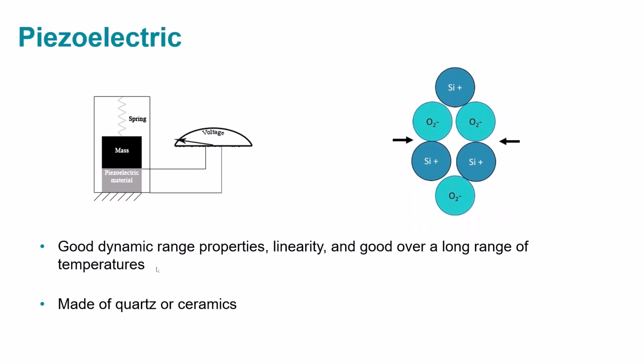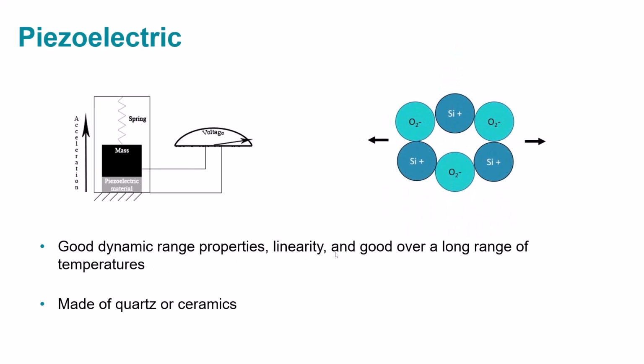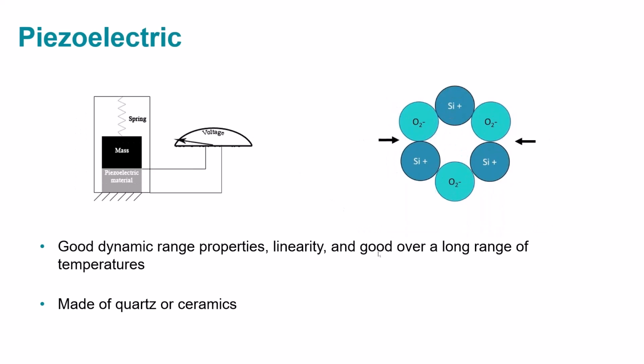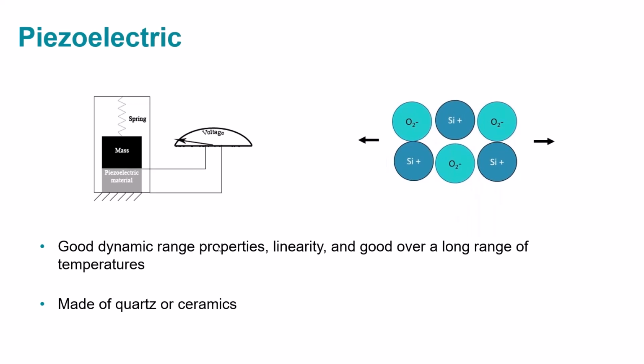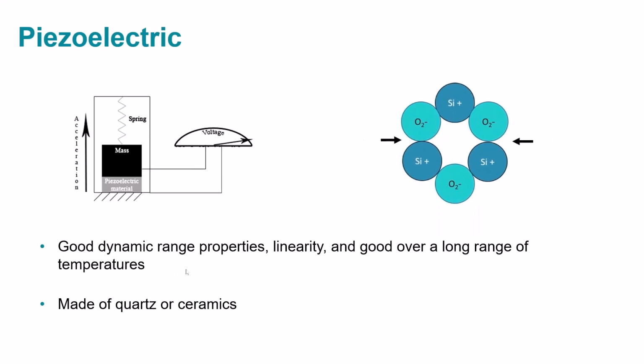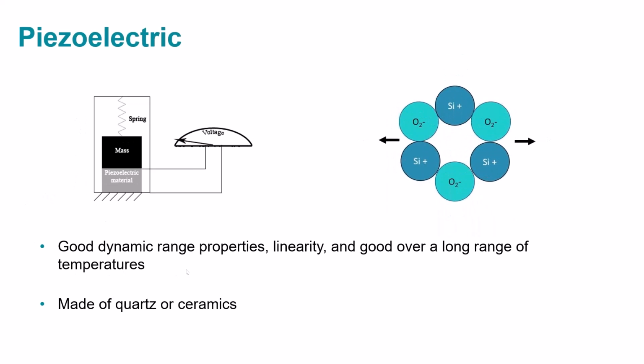Not all temperatures. Obviously, there's an upper limit, and depending on what type of accelerometer you're using, some have higher temperature ranges than others. But typically, these are pretty solid, and they're not going to drift a lot over time. So calibration on these is much easier as well.